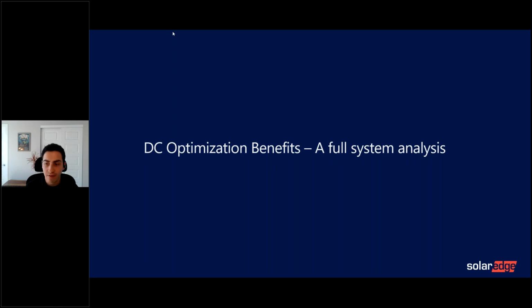What we've done is take 5 typical rooftop C&I PV systems of various sizes, and we looked at 2 design variations to be UL 3741 compliant. Obviously one of those variations uses the SolarEdge DC optimized solution, and one uses a non-DC optimized solution. We had 3 of these systems undergo an independent review and verification by Pure Power Engineering. We used the same approaches for the other 2, and those approaches for simulating production and estimating balance of system costs were also independently validated by Pure Power.